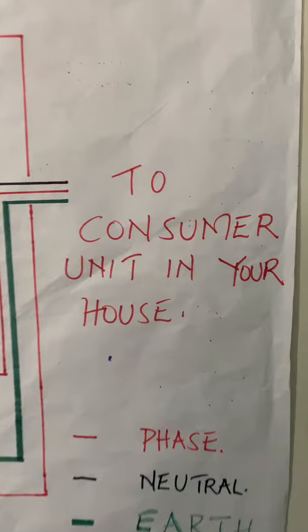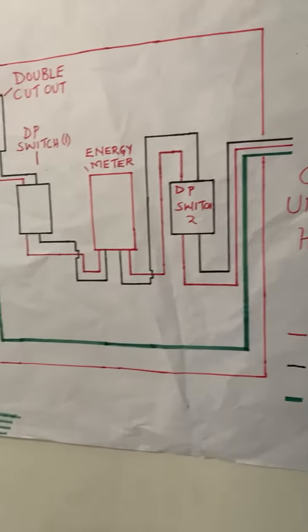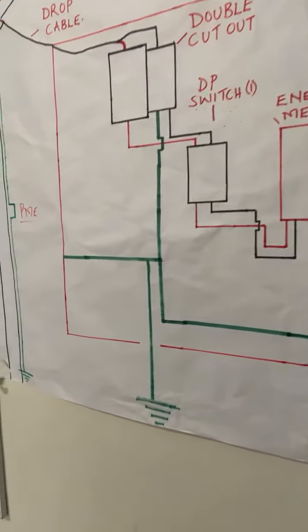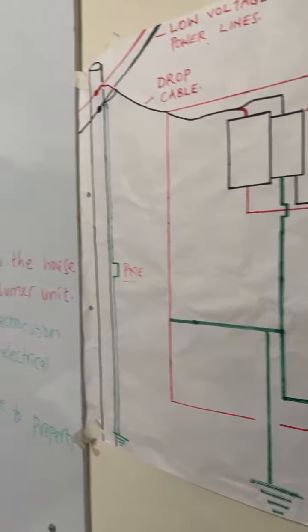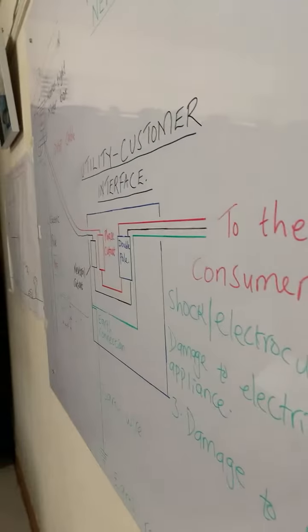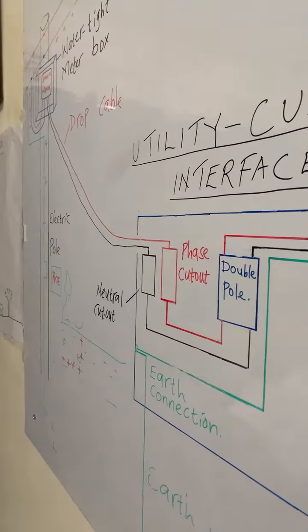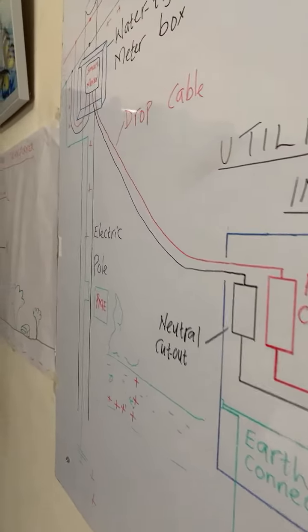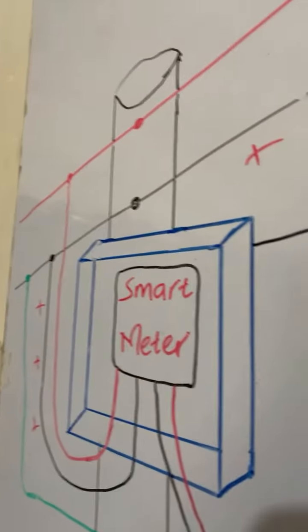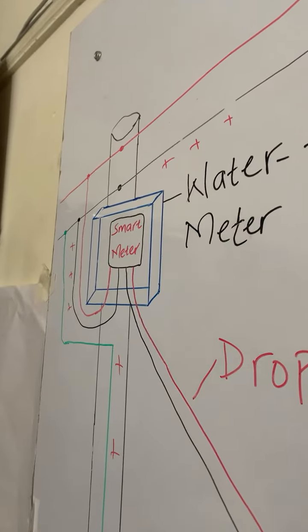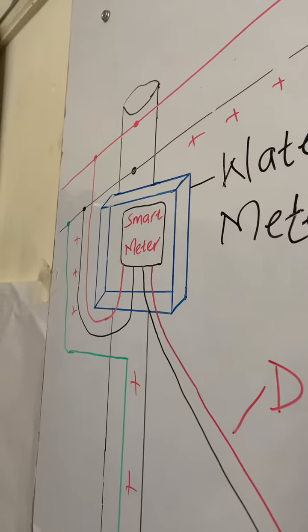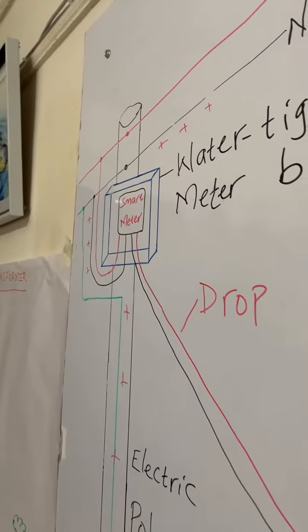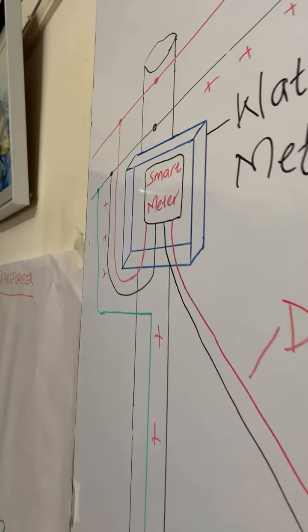At the consumer unit, you will have your earth connection connected to all the circuits in the house. Various meters are connected differently, especially when we talk about the earthing. For instance, at this particular point where we have a smart meter mounted at the pole serving the customer with power, how is the earthing connected?